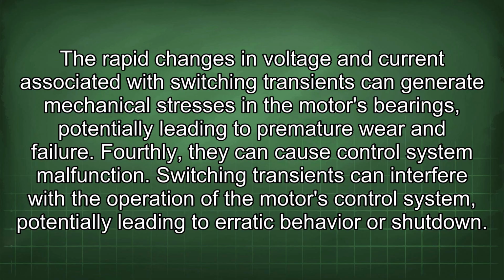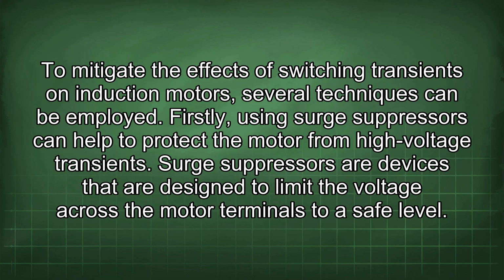The rapid changes in voltage and current associated with switching transients can generate mechanical stresses in the motor's bearings, potentially leading to premature wear and failure. Fourthly, they can cause control system malfunction. Switching transients can interfere with the operation of the motor's control system, potentially leading to erratic behavior or shutdown. To mitigate the effects of switching transients on induction motors, several techniques can be employed. Firstly, using surge suppressors can help to protect the motor from high voltage transients. Surge suppressors are devices that are designed to limit the voltage across the motor terminals to a safe level.